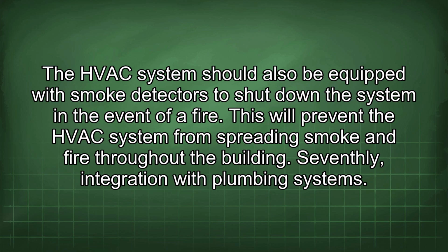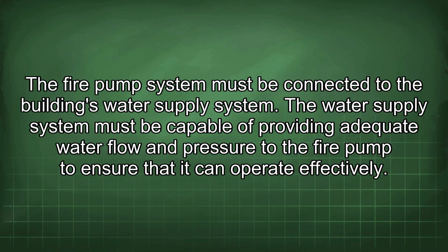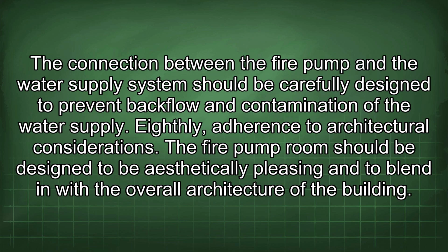Seventhly, integration with plumbing systems. The fire pump system must be connected to the building's water supply system. The water supply system must be capable of providing adequate water flow and pressure to the fire pump to ensure that it can operate effectively. The connection between the fire pump and the water supply system should be carefully designed to prevent backflow and contamination of the water supply. Eighthly, adherence to architectural considerations.